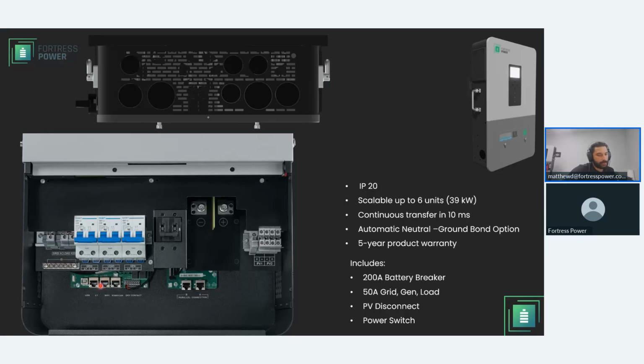Then you have your Wi-Fi CT, which in this port you will integrate your Wi-Fi dongle that is included with the system to connect it to your home router and then sync the system over the internet for monitoring purposes. And then you have the BMS port, which is RS-485 and CAN compatible. In the case of Fortress Power, we're all going to be using CAN communication, whether that's Evo Max, eForce, eBoost, eFlex Max, and any other Fortress Power 48-volt product will use CAN communication. Then you have your dry contact ports, which will allow to enable or disable your AP smart transmitter, which is not included, but this would be the area where to connect it.